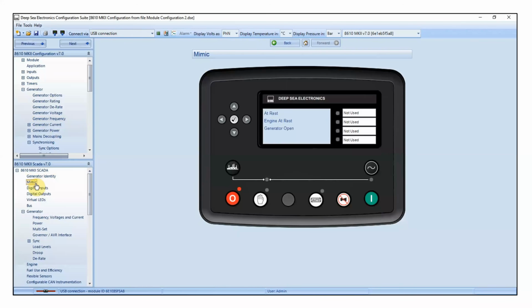So just going back, I did see that the question was, do we have some DeepSea modules with an inbuilt AVR? I believe what the customer is referring to is what the COMAP module has, which is an external AVR interface for isolation purposes. The good news is yes, all DeepSea synchronizing units, the governor and AVR terminals are isolated. The governor is isolated up to 1000 volts and the AVR is isolated up to 3000 volts. So there is absolutely no need to have any form of external interface between the DeepSea module's governor or AVR output and the respective governor or AVR for isolation purposes, because we have it all built in.